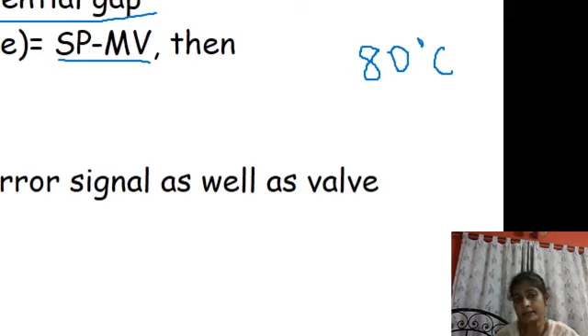Now how does it depend on the definition of error signal? Error signal is just the difference between set value and measured value. Not necessarily set point minus measured value. It may be defined as measured value minus set point. Right? So if one defines the deviation signal as measured value minus set value, then the definition of this control action will be just reverse. For that case, if error is MV minus SP, then m is minimum when e is greater than 0, m is maximum when e is less than 0. So the definition of error signal is very much important for defining the control action.